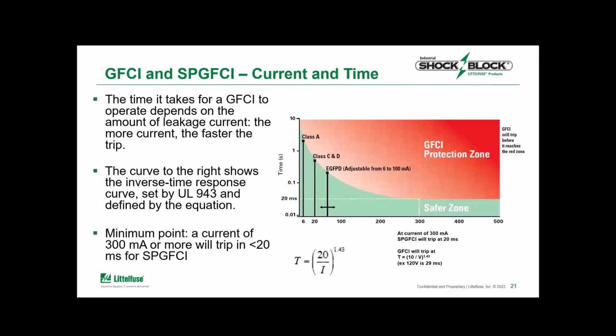Now, this inverse time curve is designed to ensure the GFCI will trip faster as the current gets higher. And if you recall that previous human danger curve, that's because the longer the current is there, the higher the risk factor can be.